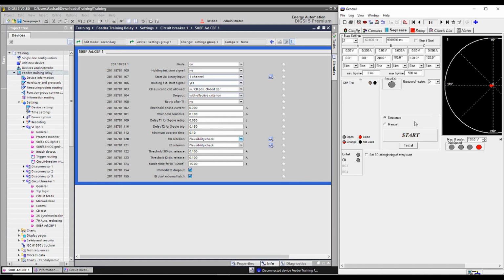Prove it to us. To prove it to you, I need to inject 3 stages. In the first, normal state; the second state, for example, I'll set its time to 200 milliseconds, and it will have the current. The third state, I will inject with a very long time, and I will set the contact here to not used.